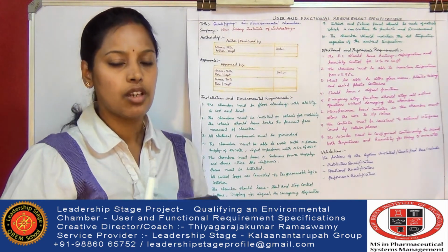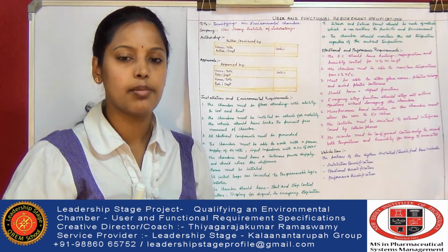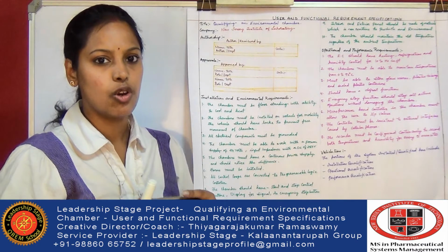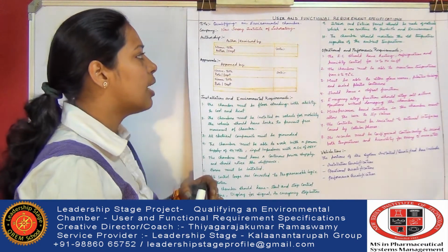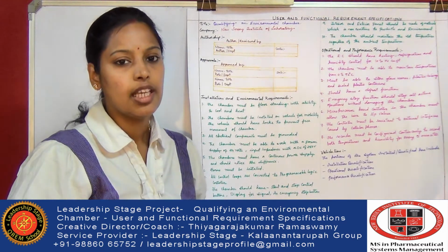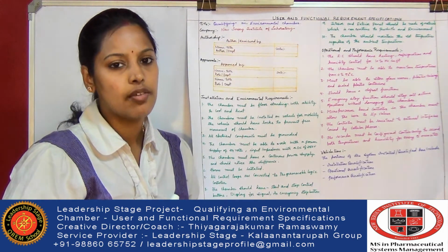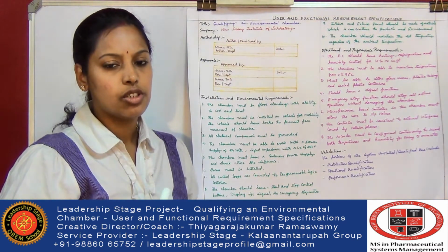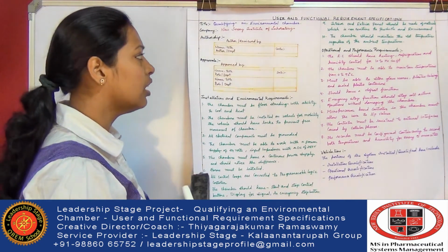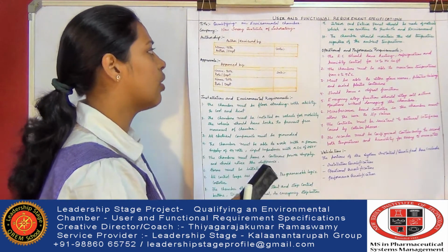Due to exposure to air, it may lead to rust, so such things should not happen. And the chamber should maintain a set temperature regardless of the ambient temperature. Irrespective of the temperature outside, it should have a constant temperature of its own environmental chamber. These are the installation and environmental requirements.